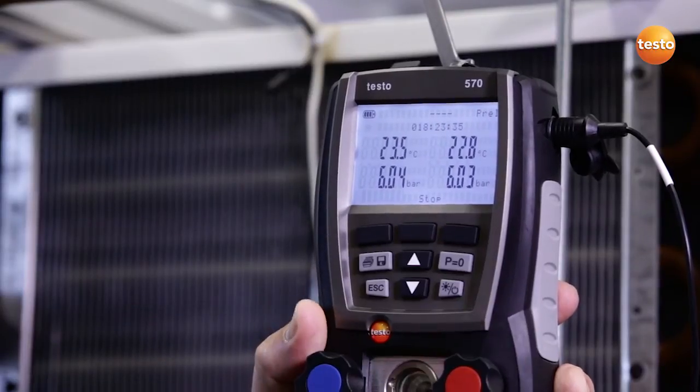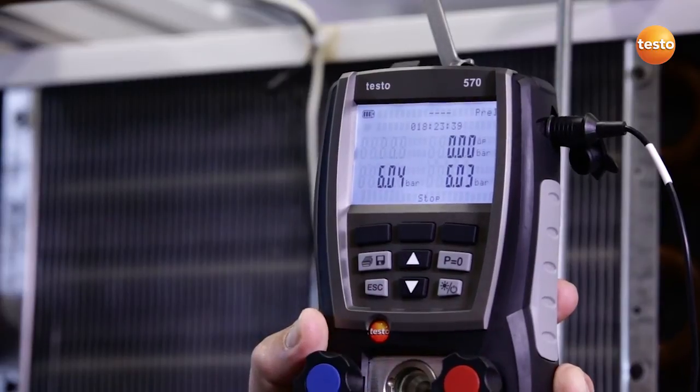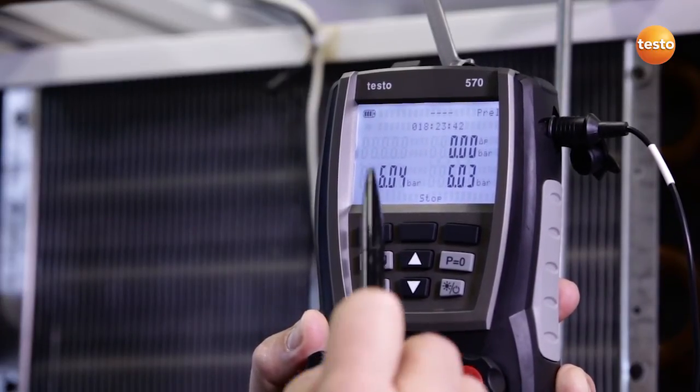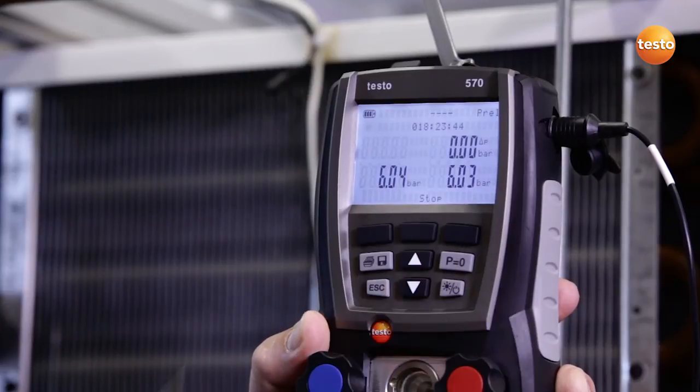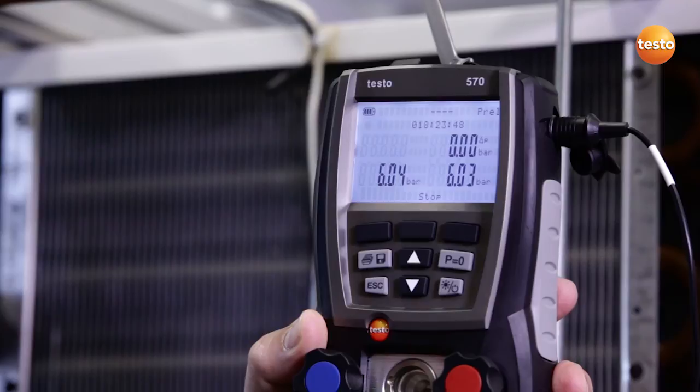This identifiable slight pressure drop could indicate a leak, however, thanks to the temperature compensation, the instrument shows us a pressure drop of 0.00 bar. This means the result of the pressure drop test is positive.